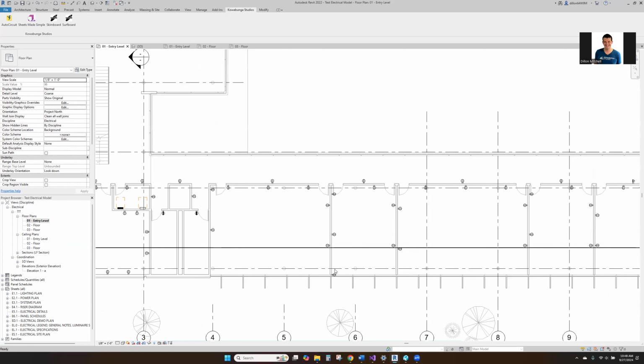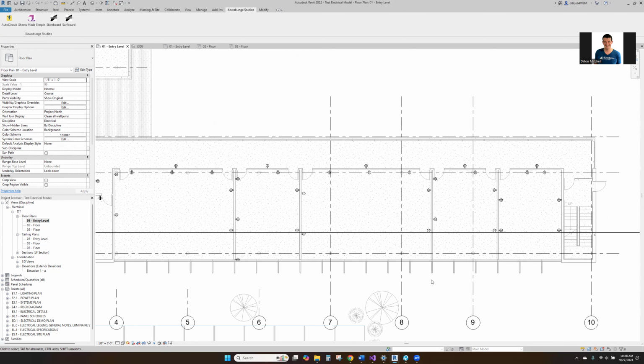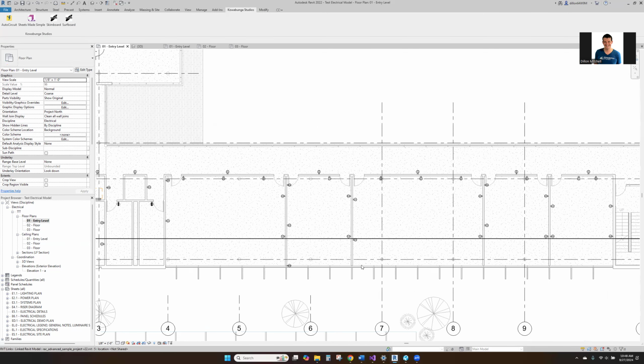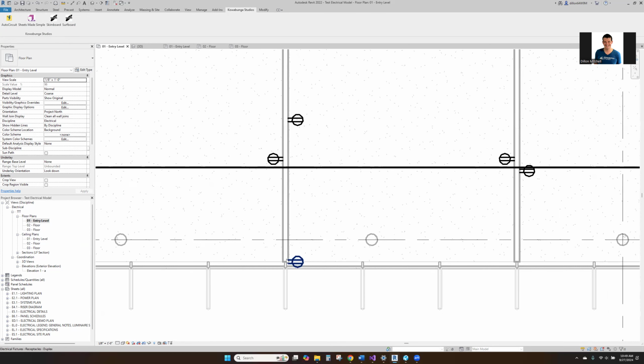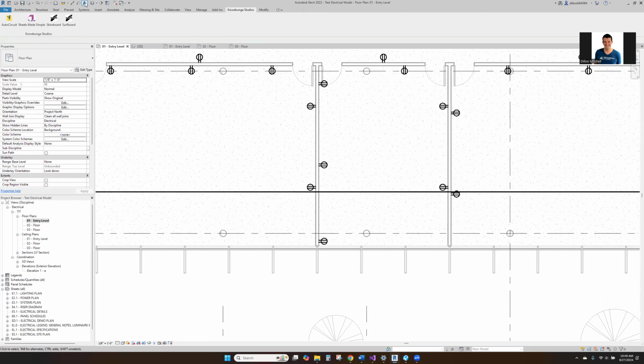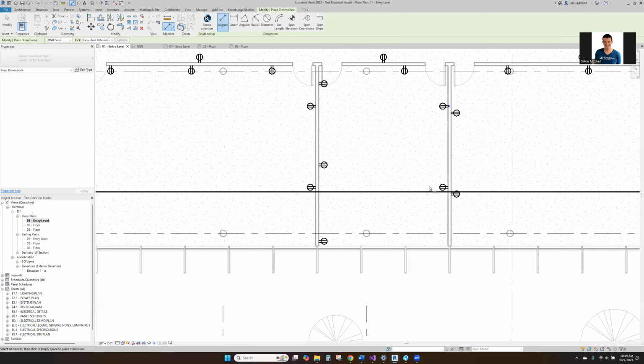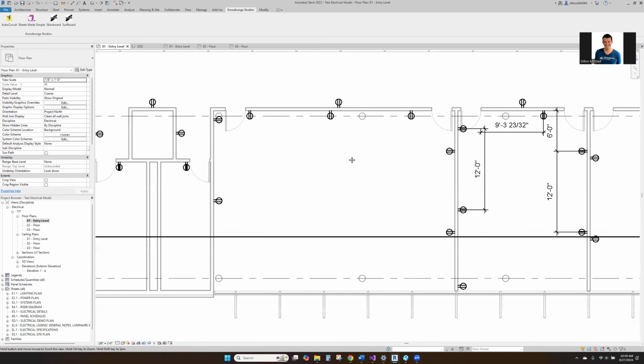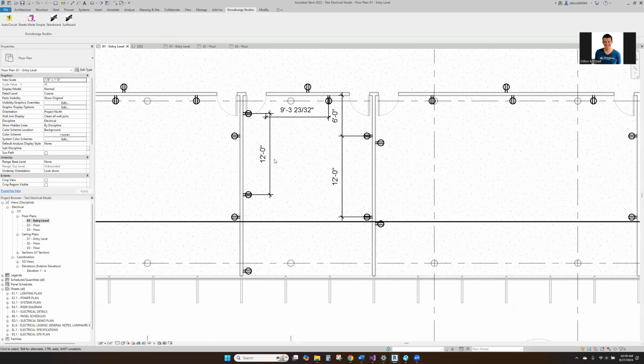And then another big thing to note is that for this curtain wall, we're not going to place any devices on that curtain wall. This is really the closest that we're going to get to placing a device on curtain wall, because again, we are doing our perimeter spacing here. So we've got our 12 feet on center with these devices. So that's a super big thing to note as we go through this. And then again, you've got your 6 feet from door, 12 feet on center, and it'll choose one door and then go from there. That is how this is laid out.